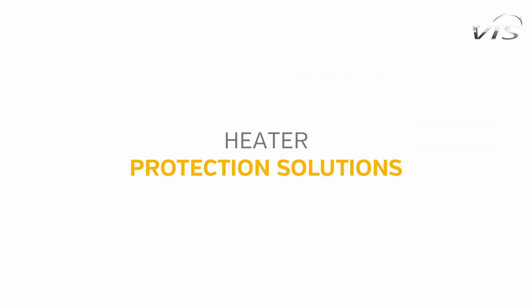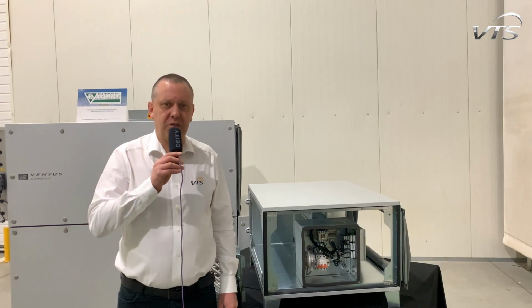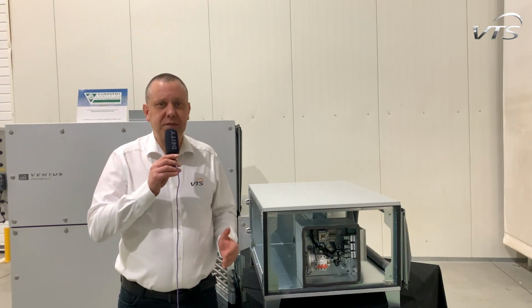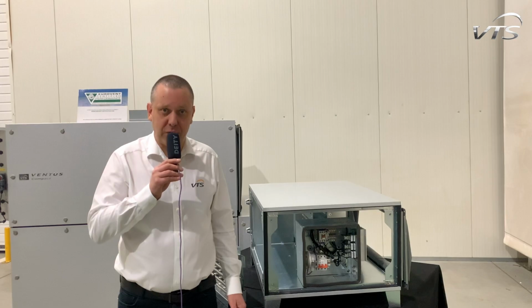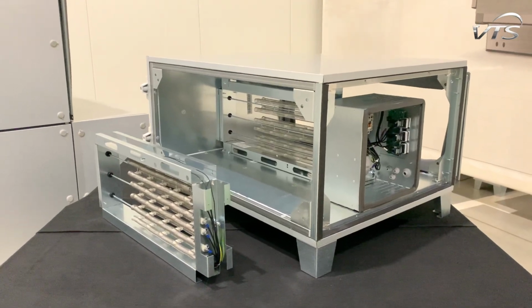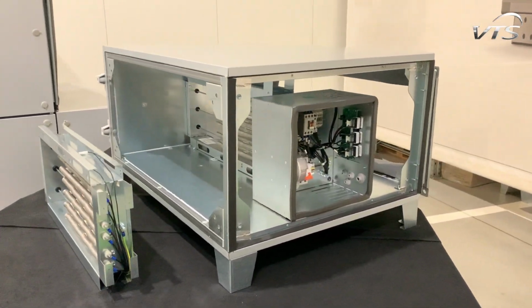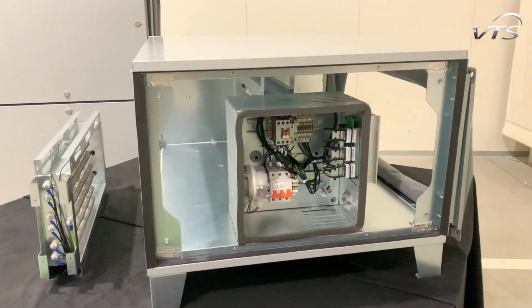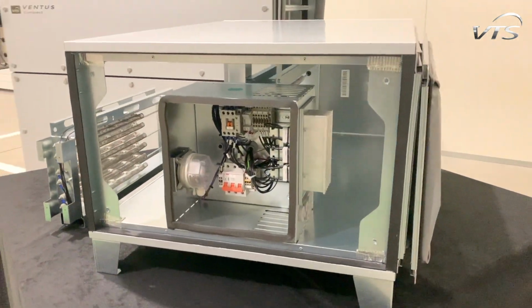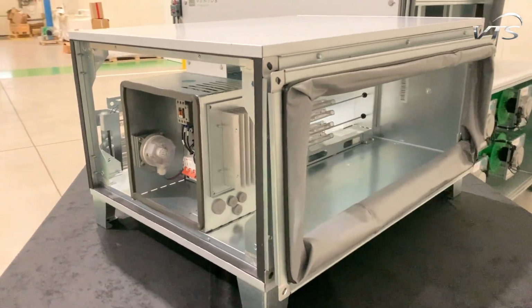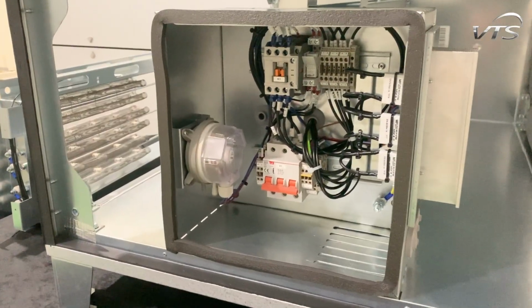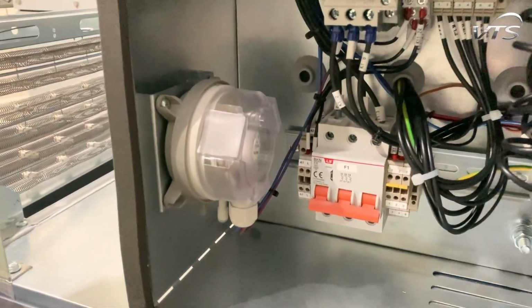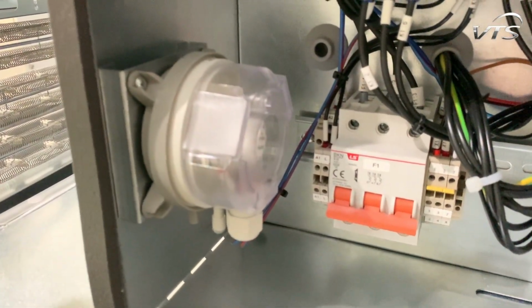Heater protection solutions. Our new electric heaters integrated with the controls are self-sufficient in terms of the safety of operation. If you take a look inside the junction box, you will find a factory-installed differential pressure switch connected to the air handling unit's fan section. If there is no pressure difference sensed upstream and downstream of the fan, the heater's control understands it as a lack of airflow and immediately shuts the heater down.